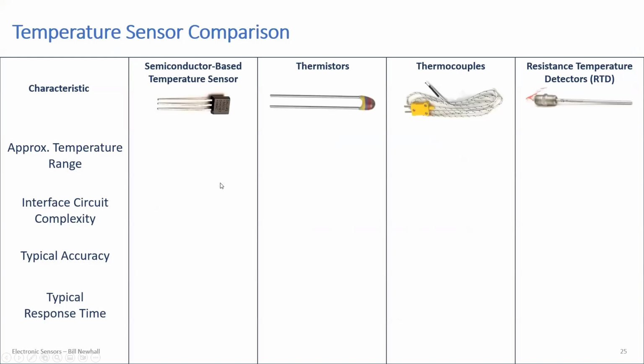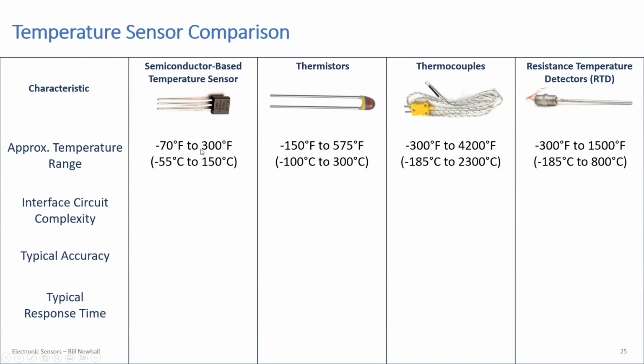So here's a summary of the temperature sensors we talked about: the semiconductor-based sensor, a thermistor, a thermocouple, and an RTD, along with their ranges. The semiconductor-based temperature sensor has the narrowest range. It's typically used on circuit boards to measure board temperature, and maybe in thermostats since that falls within its range. You couldn't use it for an oven temperature sensor, since it only goes up to about 300°F. It's a relatively narrow range, but good for applications in a pretty benign environment.